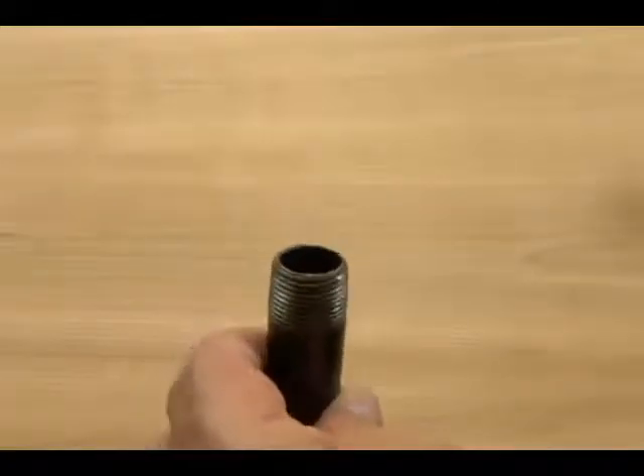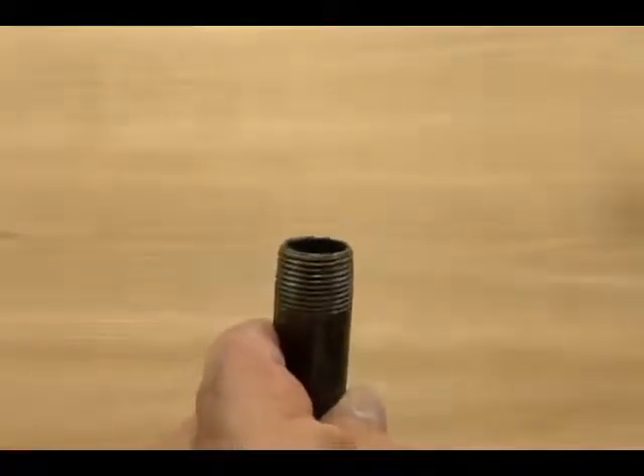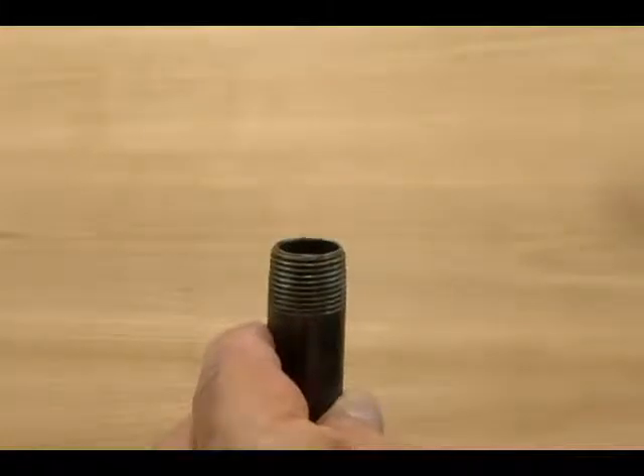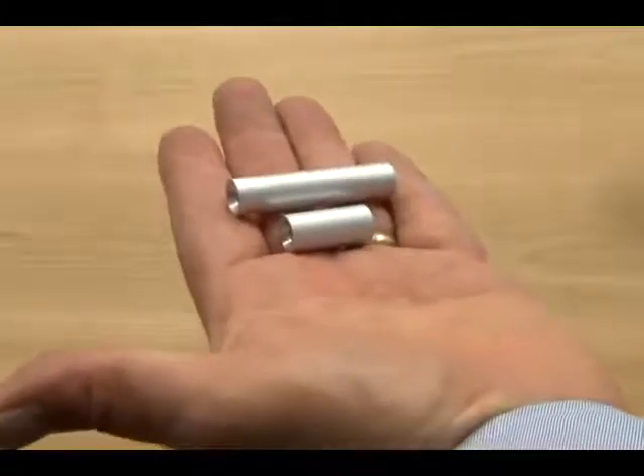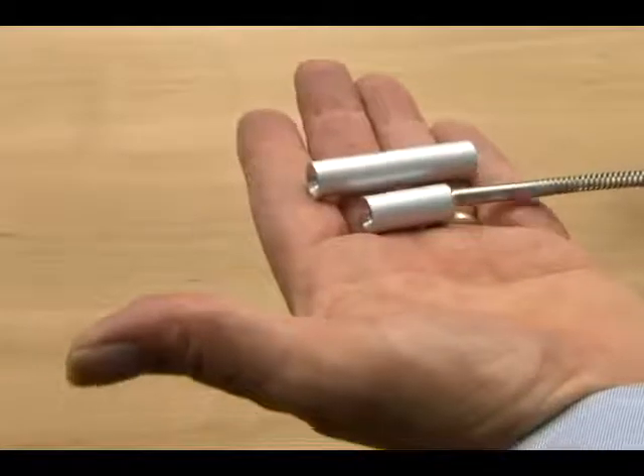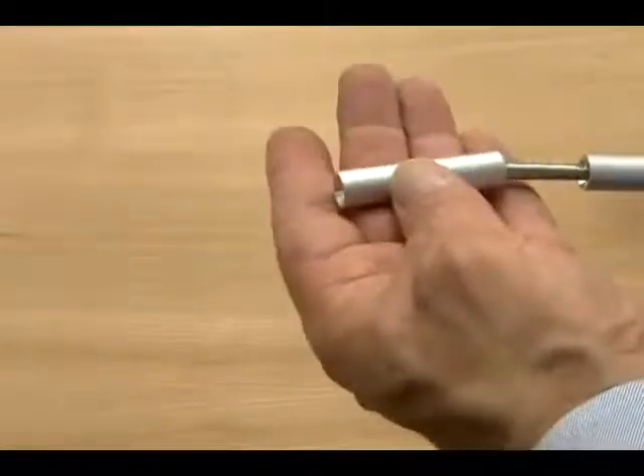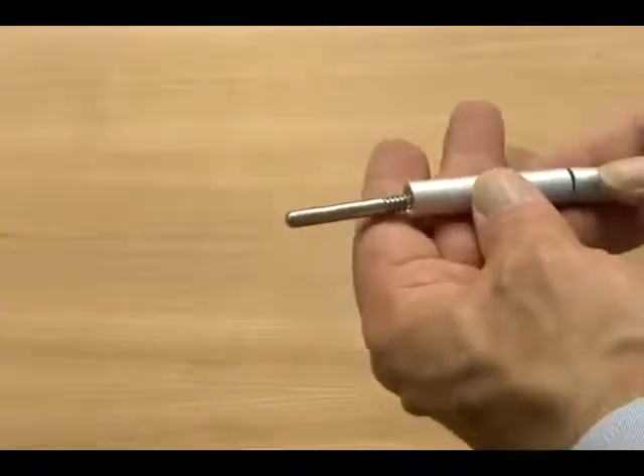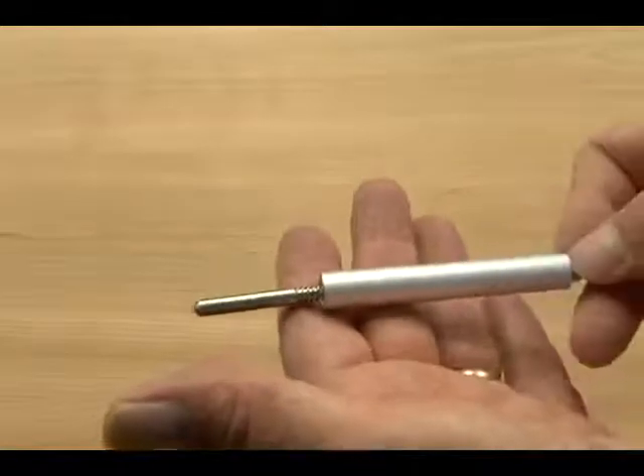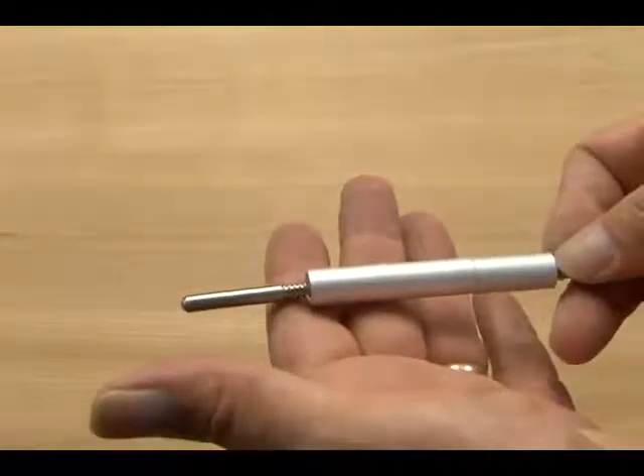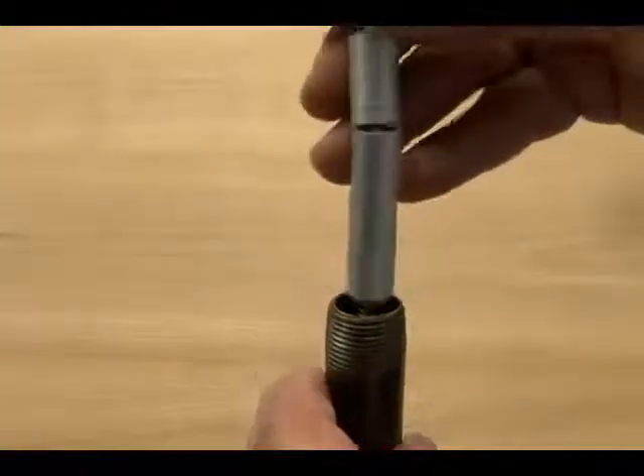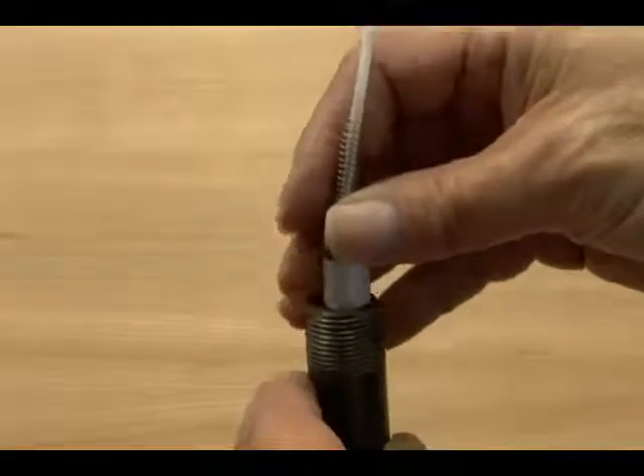If the connection between the thermowell and housing is a section of half-inch pipe or heavy wall conduit with a full internal bore, these spacers will help keep the worm spring centered and ease insertion. Simply stack in as many as required to fill the space. The spacer's internal bore is large enough for the probe to pass through, so they can stay in place in the pipe. They're included in each kit and can also be purchased separately.